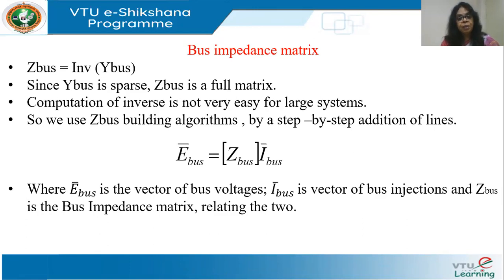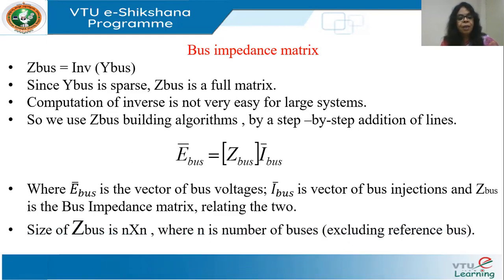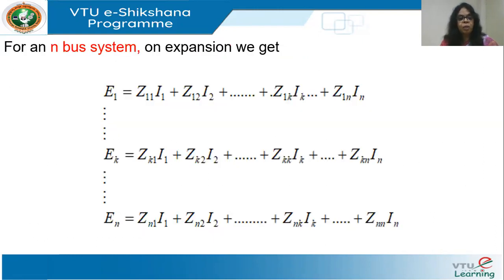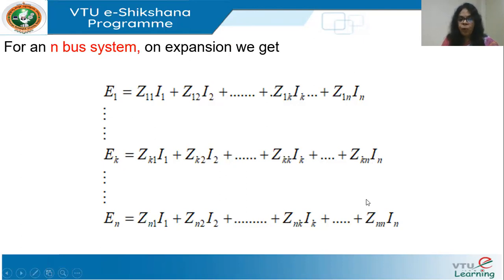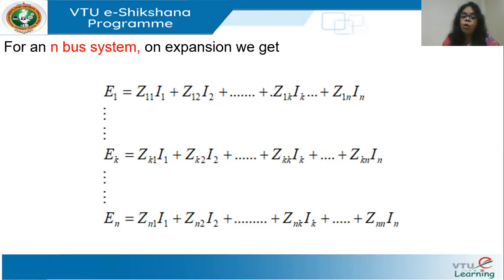E_bus is the vector of bus voltages, I_bus is the vector of bus injections, and Z_bus is the bus impedance matrix relating the two. The size of Z_bus is N×N where N is the number of buses excluding the reference bus. On expansion, we get E1 = Z11·I1 + Z12·I2 + … For any bus K: EK = ZK1·I1 + ZK2·I2 + … + ZKN·IN. The potential of the reference bus is always taken to be zero — just as in nodal analysis in network theory, all voltages are represented with respect to the reference bus.